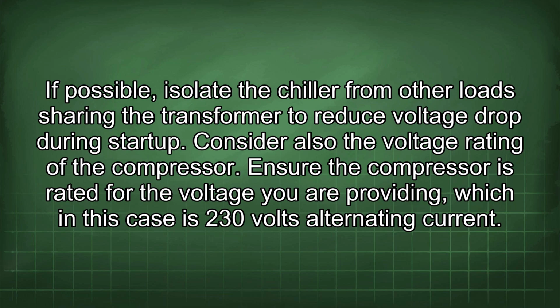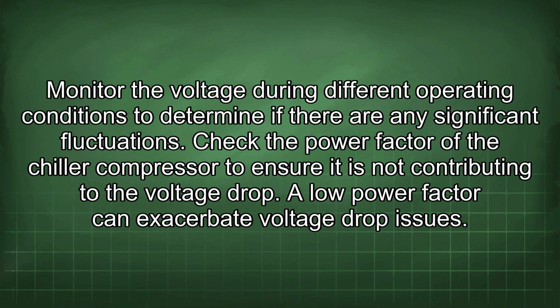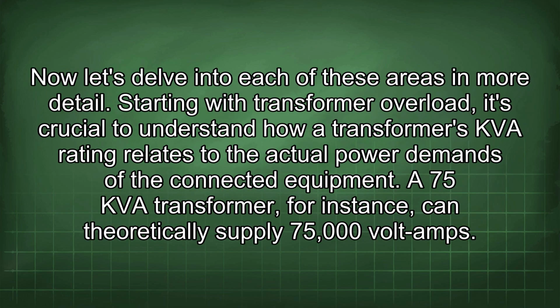Consider also the voltage rating of the compressor. Ensure the compressor is rated for the voltage you are providing, which in this case is 230 volts alternating current. Monitor the voltage during different operating conditions to determine if there are any significant fluctuations. Check the power factor of the chiller compressor to ensure it is not contributing to the voltage drop. A low power factor can exacerbate voltage drop issues. Now let's delve into each of these areas in more detail.